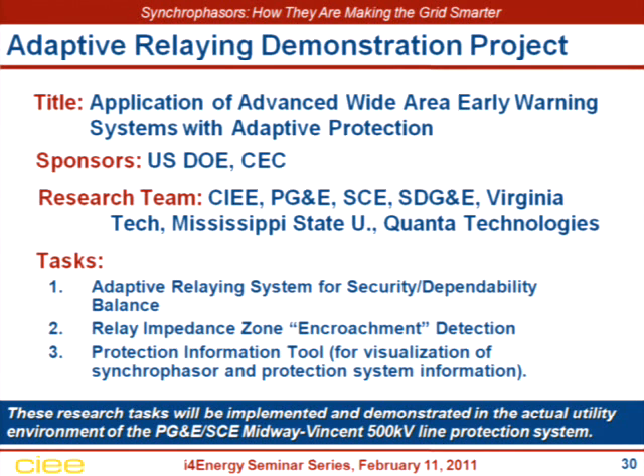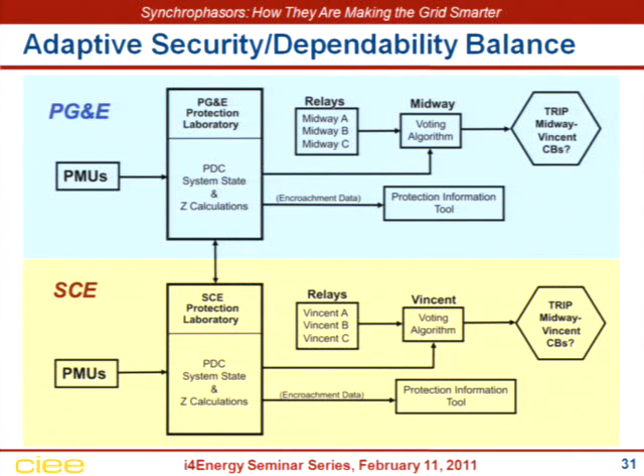And then we're doing some visualization work with something called a protection information tool, which is a way of visualizing the impedance or the protection information. And we're doing this on an actual line. This is sort of a schematic of how it works. We have the Midway to Vincent 500 kV line. PG&E owns Midway, SCE owns Vincent. They both have operating control centers that have protection laboratories, as they're called.